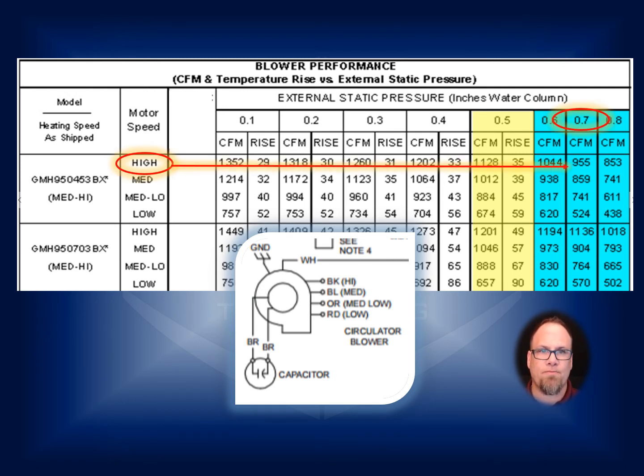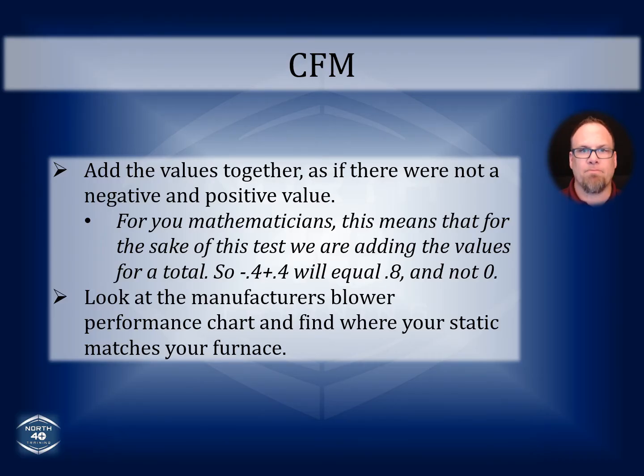Here's your example. If you look at this, we had 0.7 inches of static on high fan speed, 0.5 inches of static, taking your measurement, of course, before the blower and after the blower. Adding those together, that came up to 0.7. You go over to this chart, 0.7 equaled 955 CFM. Okay, so that is a direct value that is very easy to measure and then also to manipulate, because you can change your fan speed to one lower than that very easily. You just change the speed taps on the blower.